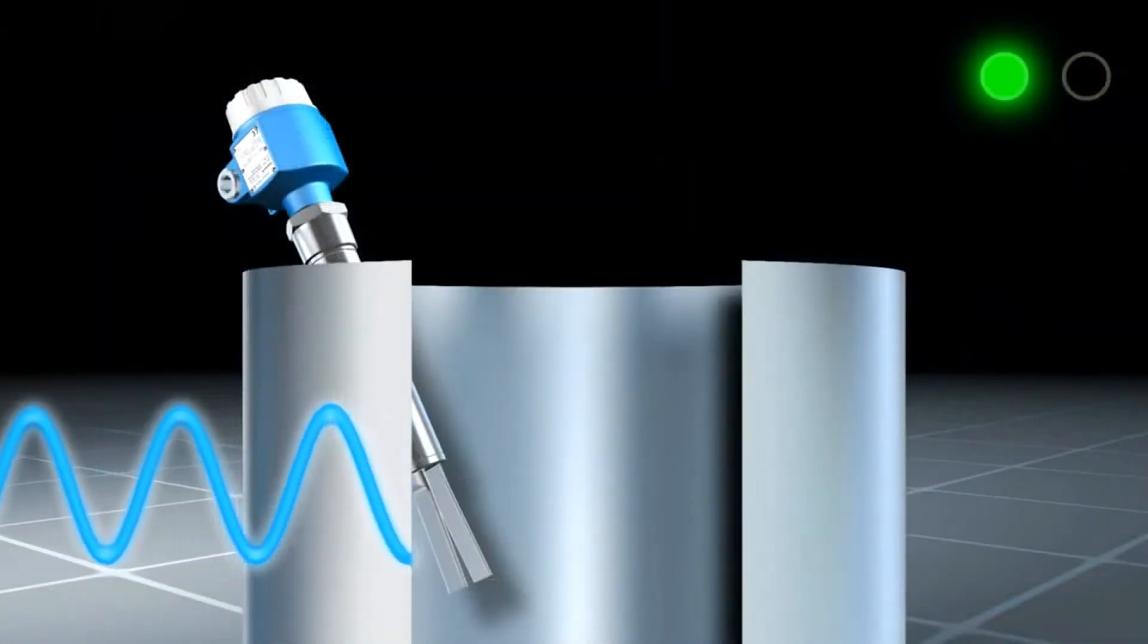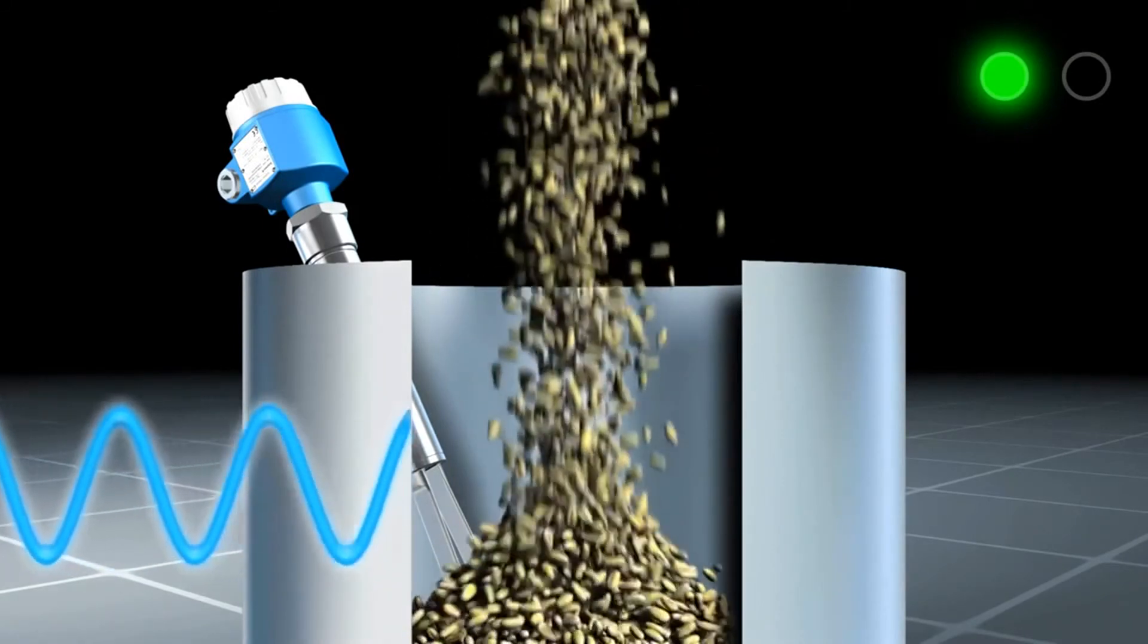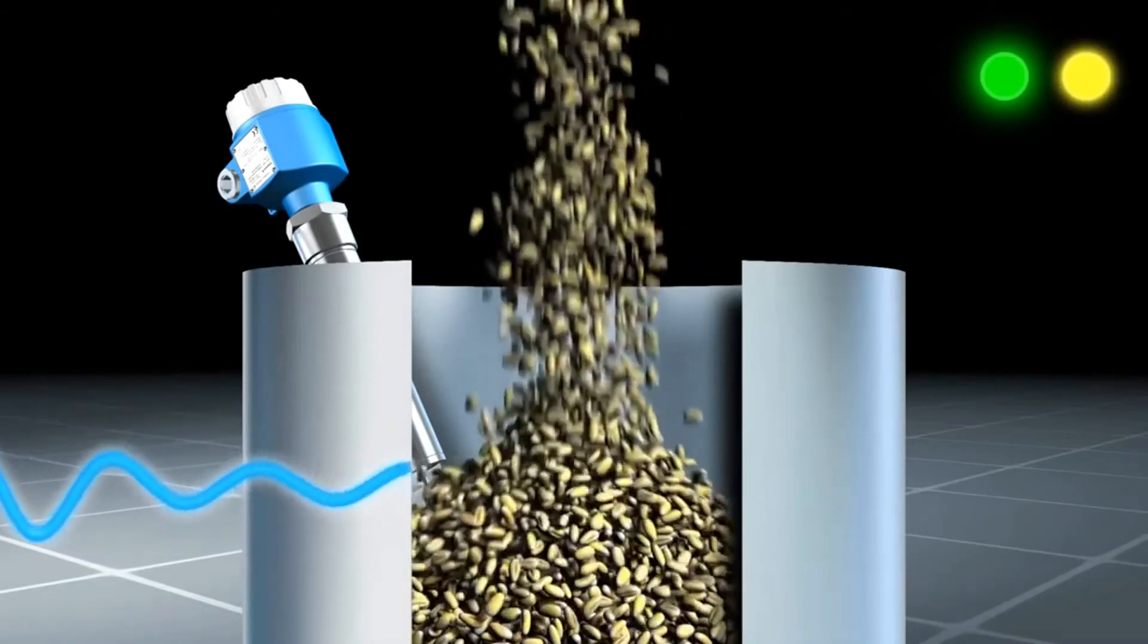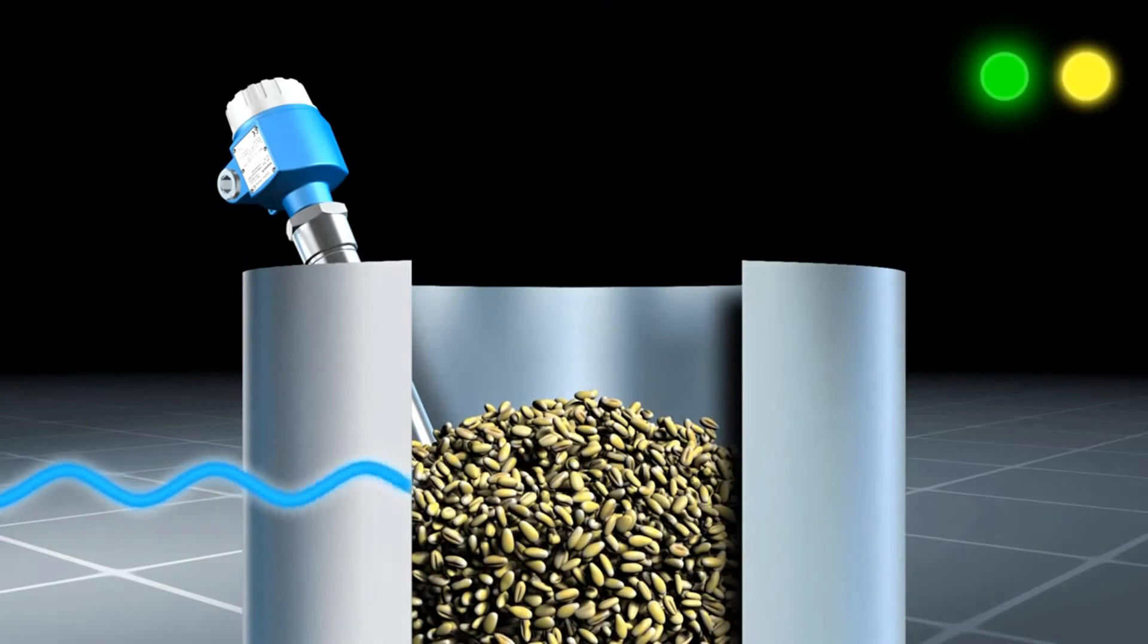In solids measurement, only the piezoelectric stack drive is used. As the bulk solids cover the fork, the oscillation is damped. This changes the amplitude of the oscillation. The change is analyzed and converted into a switching signal.